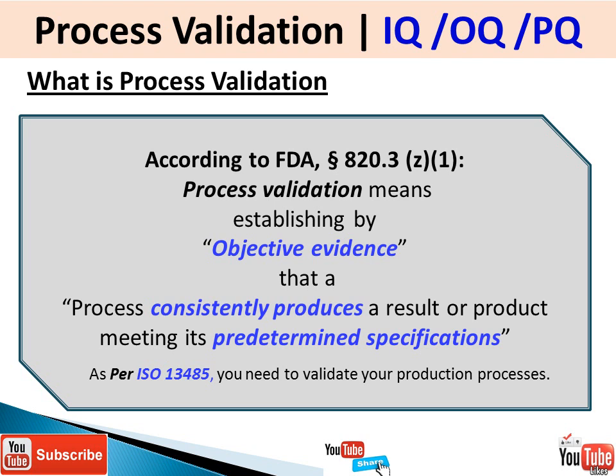Let me break this definition down to the component level. Objective evidence is a documented collection of facts, data, and statistical analysis that serves as a basis for concluding that your process is operating in a validated state. The meaning of 'consistently produces' goes back to the idea of process capability and process stability — if you can achieve both, you are able to consistently produce good parts.